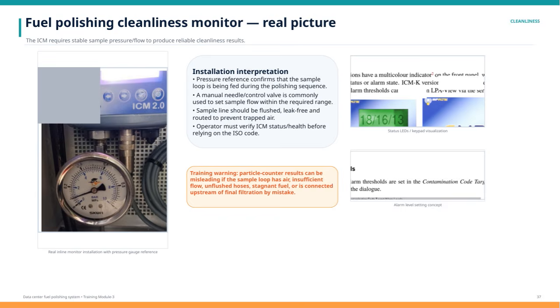Looking at the installation, you can see the inline monitor paired with a pressure gauge. This pressure reference is essential because it confirms that the sample loop is actively being fed during the polishing process. Typically, a manual needle or control valve is used to adjust the sample flow to fall within the required range. It's also critical that the sample line is properly flushed, free of leaks, and routed to avoid trapped air. Any air in the line can disrupt the sample quality and lead to false readings.